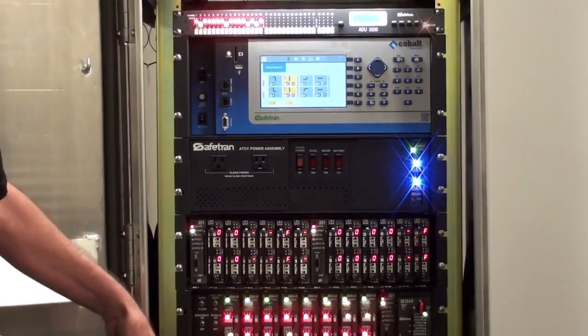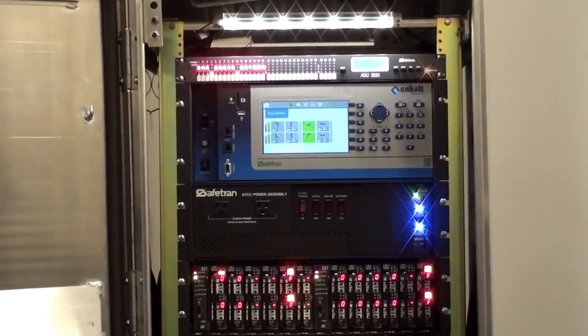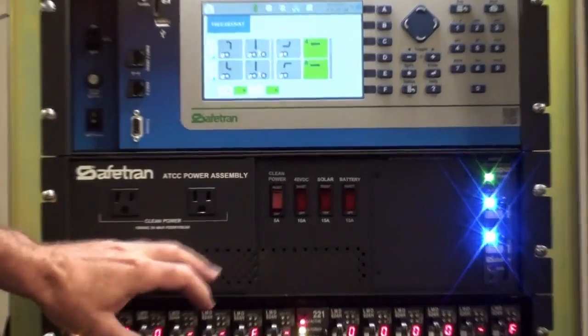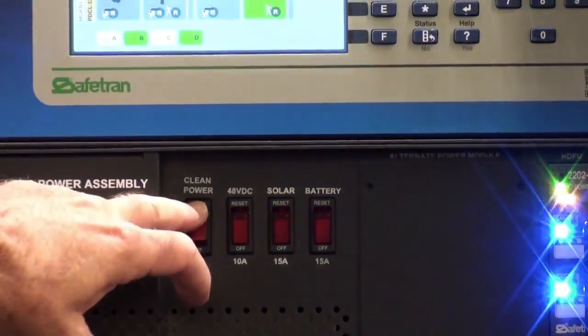For example, you can remove the input assembly, output assembly, controller, and auxiliary display unit, or ADU, from the cabinet, and it will stay in flash. This keeps the intersection in a safe state during maintenance or equipment replacement.